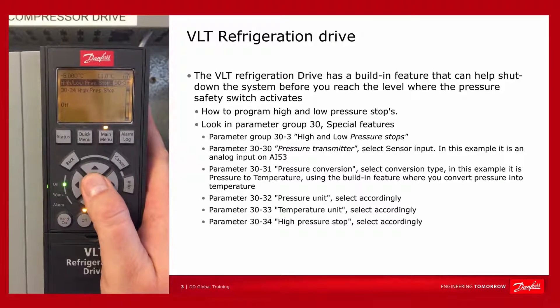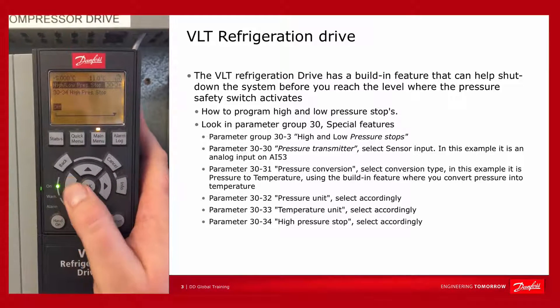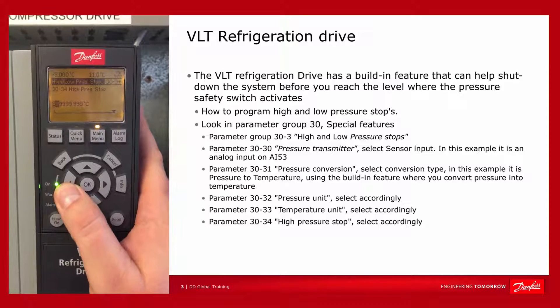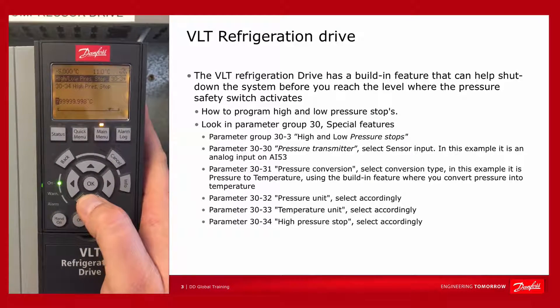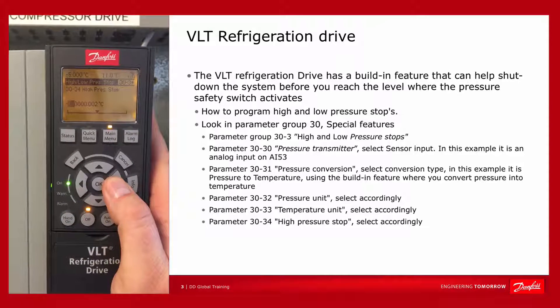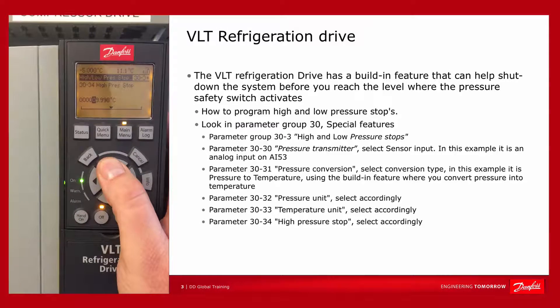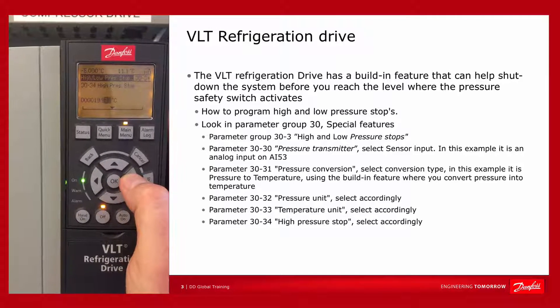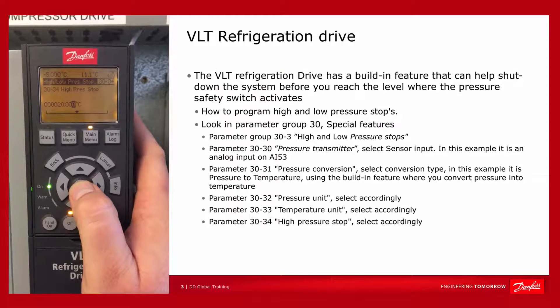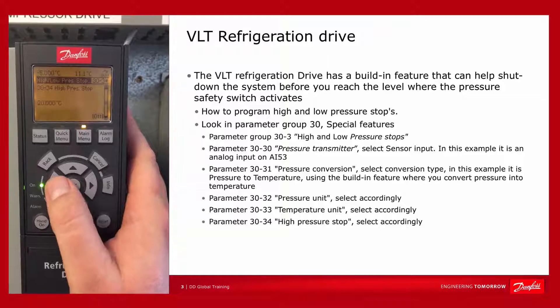Then at which level should you stop the drive? We want to accept a temperature of 20 degrees in this case, so let's program 20 degrees. That's the maximum temperature we will allow, and then we will make a safe shutdown on the system.